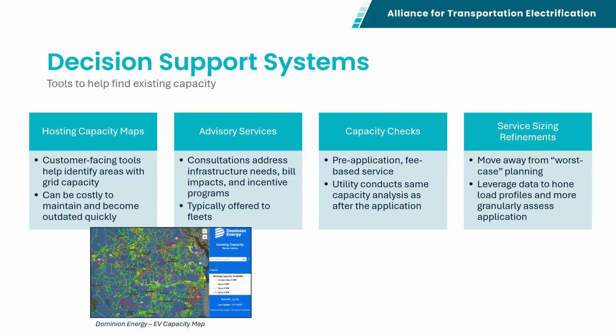One idea gaining prominence, and about to be standardized in California in particular, is capacity checks. Before submitting a service application, the customer can go to the utility and pay a fee pre-application to get a capacity check at the location they're interested in building. That's pretty expensive, because the utility goes through the same analysis as they would after the application. But it can show the customer whether there's potential for that site before they do the more in-depth engineering needed to complete a full application. That's something gaining interest.